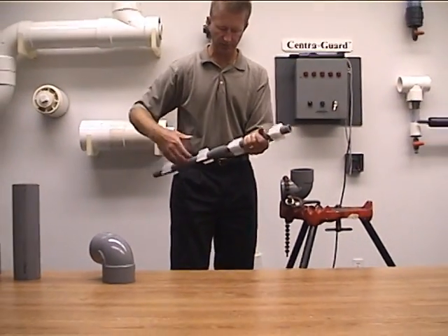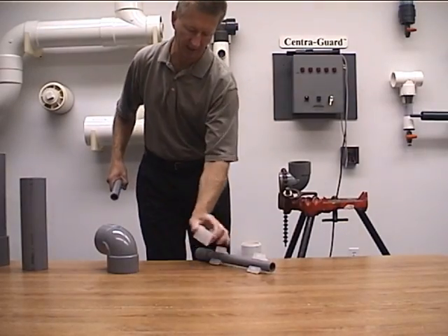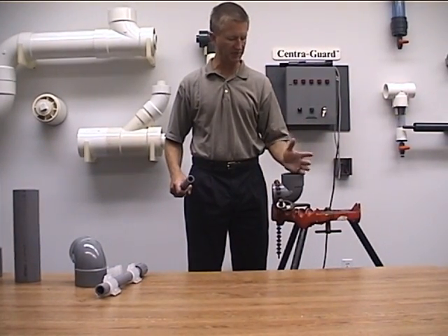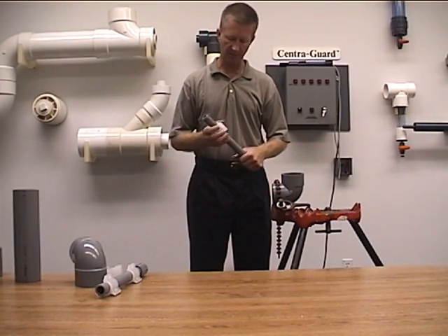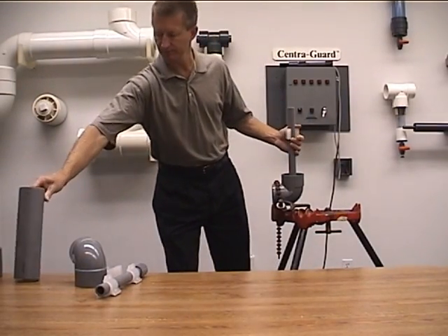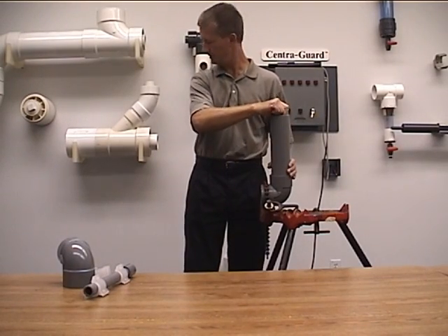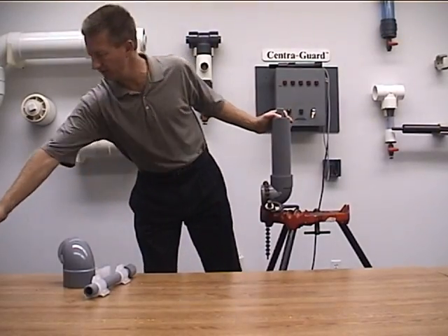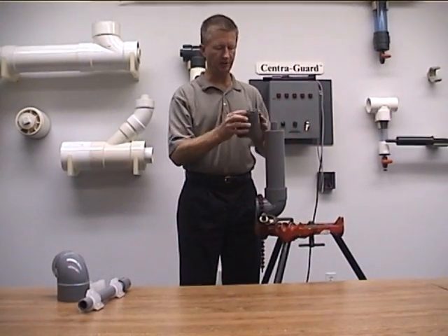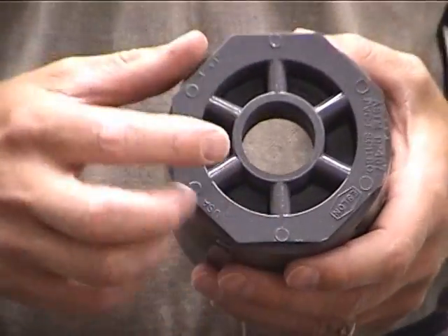The final thing I'd like to show you is typically how a system is terminated. In most systems, you're either going to be coming up to grade, through a basement floor, or through a basement wall, and you're going to want to stop the double containment and install a termination fitting. We are going to do that by solvent cementing in our carrier pipe and having the containment pipe solvent cemented in as well. The termination fitting is simply a coupling that has been fitted with a bushing in it — it is through-bore.